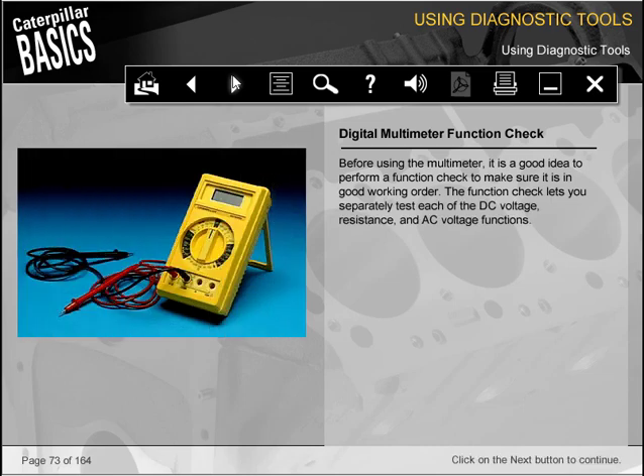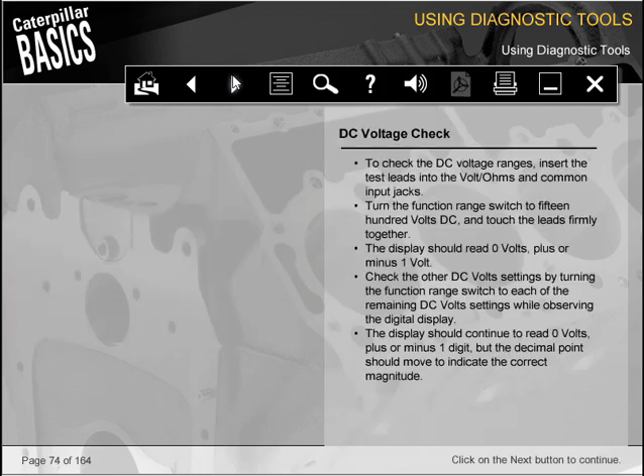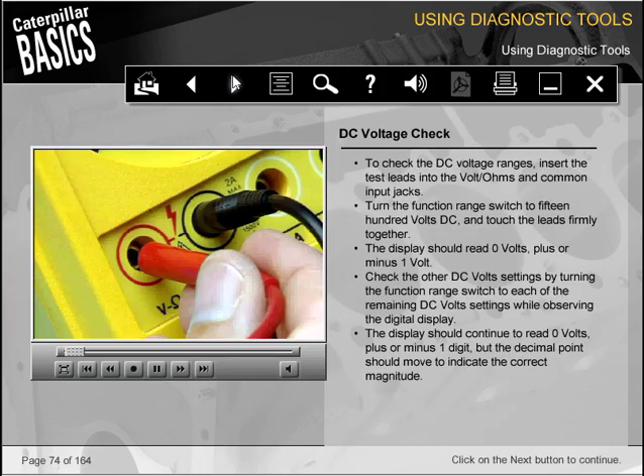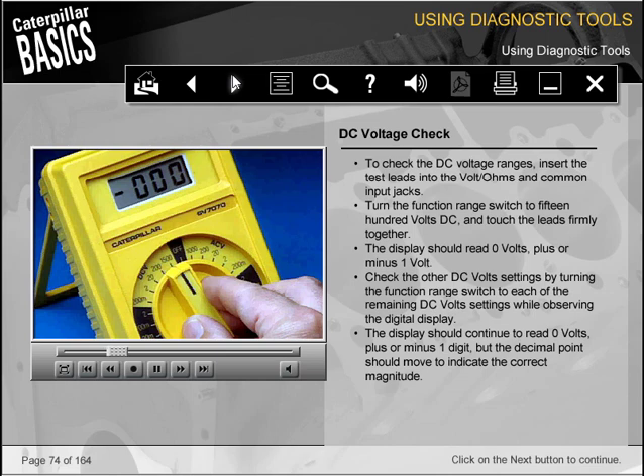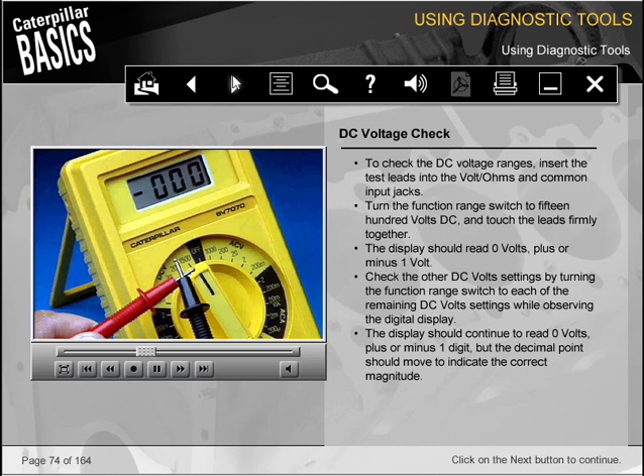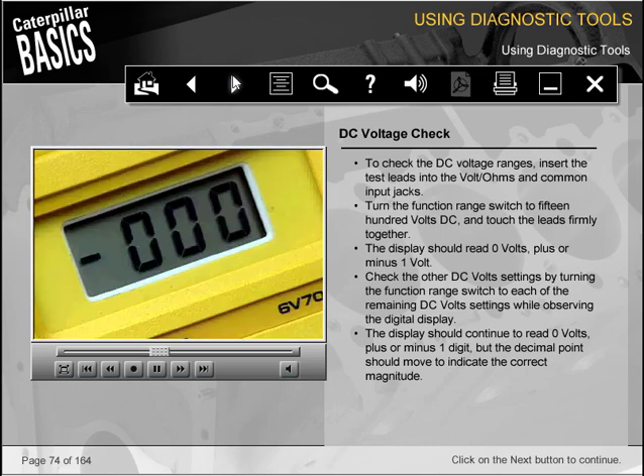Before using the multimeter, it is a good idea to perform a function check to make sure it is in good working order. The function check lets you separately test each of the DC voltage, resistance, and AC voltage functions. To check the DC voltage ranges, insert the test leads into the volt, ohms, and common input jacks. Turn the function range switch to 1500 volts DC and touch the leads firmly together. The display should read 0 volts, plus or minus 1 volt.